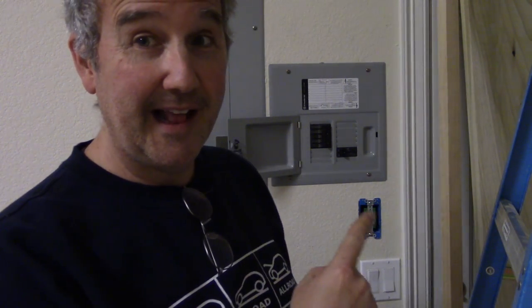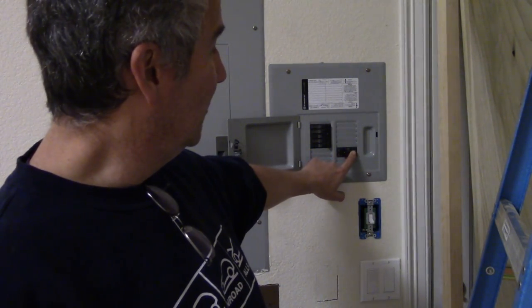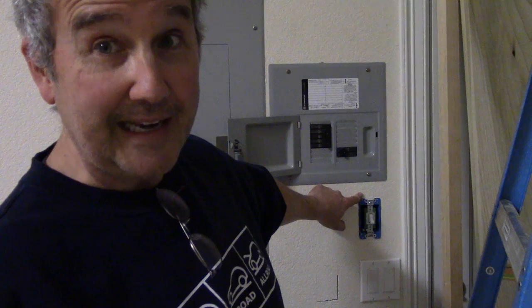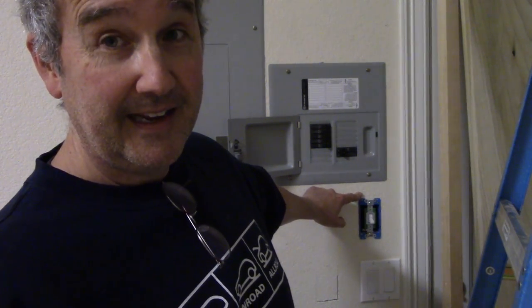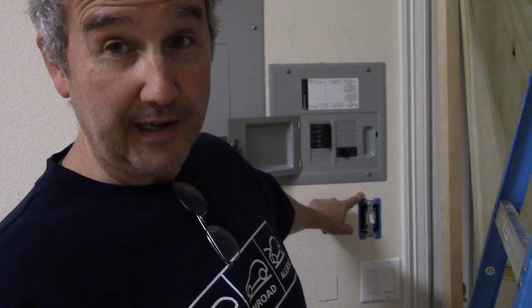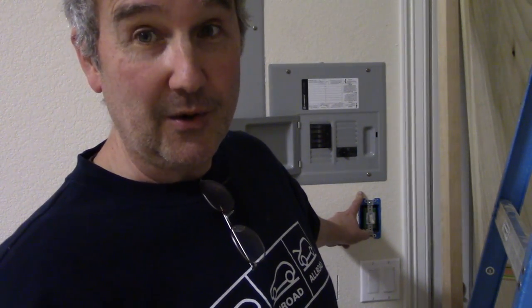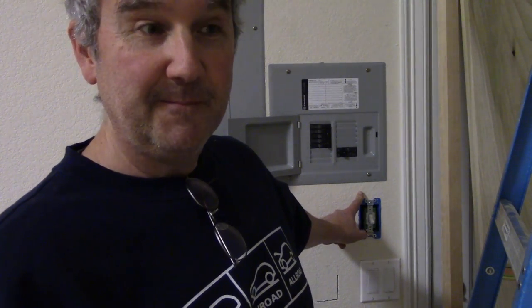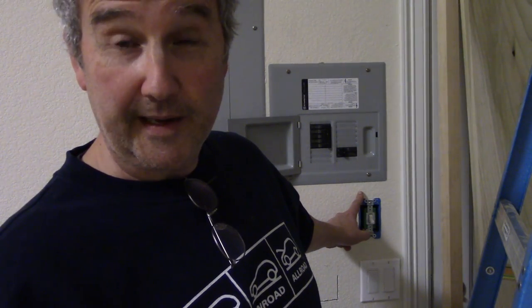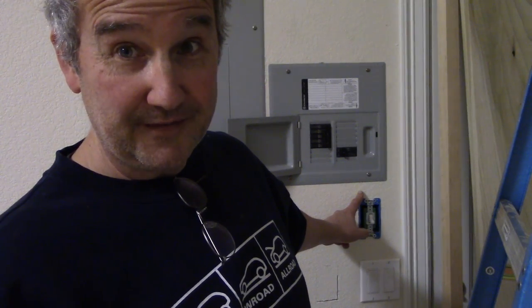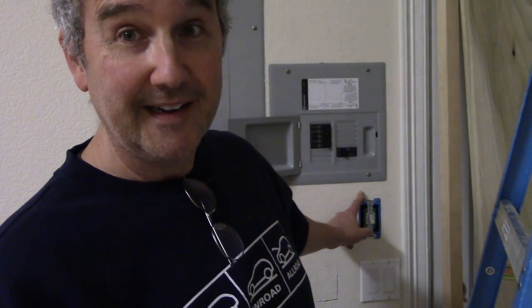I am using a 10-gauge wire, which is the orange stuff. Yellow is 12-gauge, and the white stuff is 14-gauge, which is what you see all the time in your house. That can typically handle about 15 amps. The yellow stuff is 20 amps, and the orange stuff is 30 amps. I need 30 amps to run the 5,000-watt heater. The heater in the other garage is 7,500 watts and it needed 8-gauge wire. That was wicked expensive, I needed about 60 feet to do it. It was like $150 just in wire.